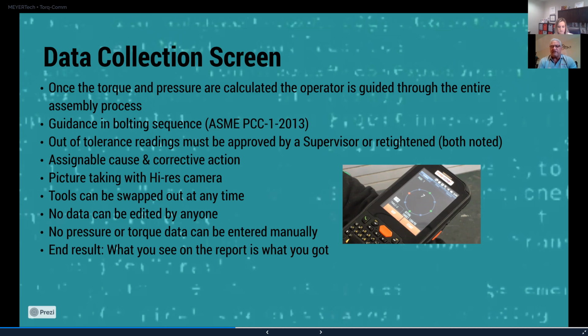All this information goes into that final report: assignable cause and corrective action. You walk up to a pipe flange, let's say all the bolts are rusted. That would be my assignable cause, rusted bolts. You can then have a pull-down pick list with all your possible corrective actions, such as wire brushing off the bolts, cutting them off, swapping them out, whatever the case may be. So they enter the corrective action, and on the back of the unit is a high-res camera, so you can take a picture of that corrective action, and all of that information goes into the final report.